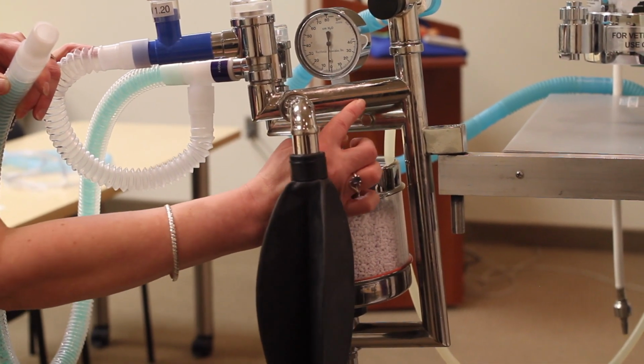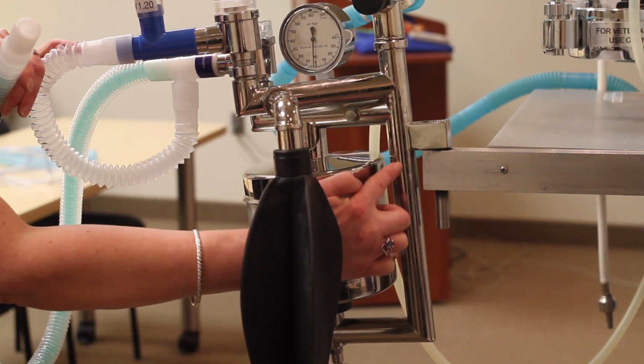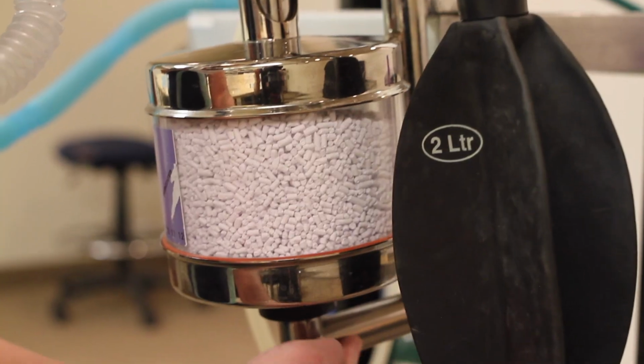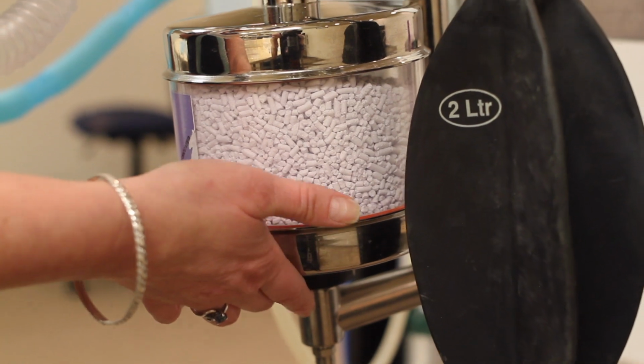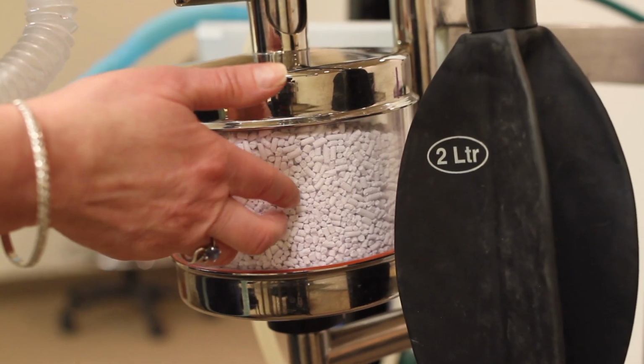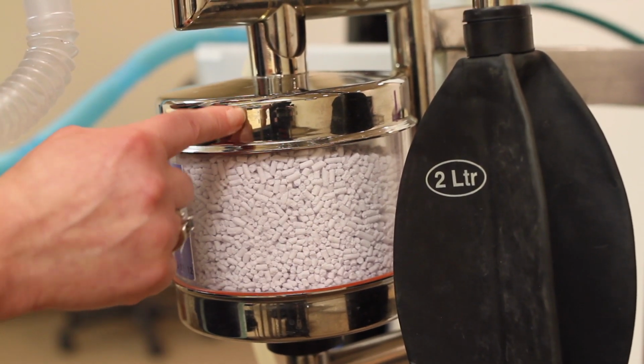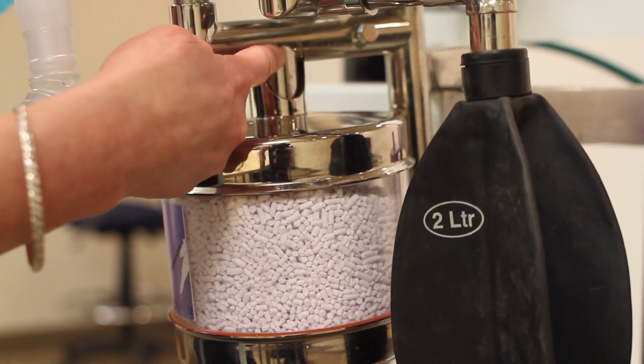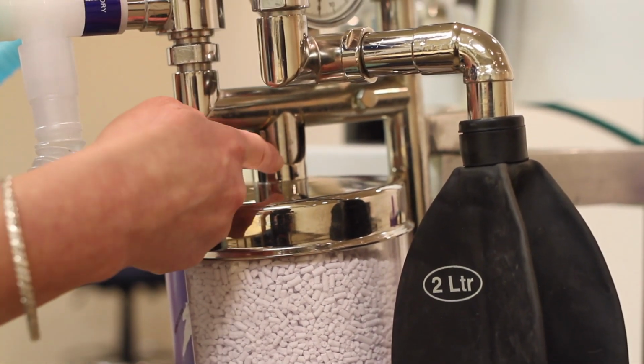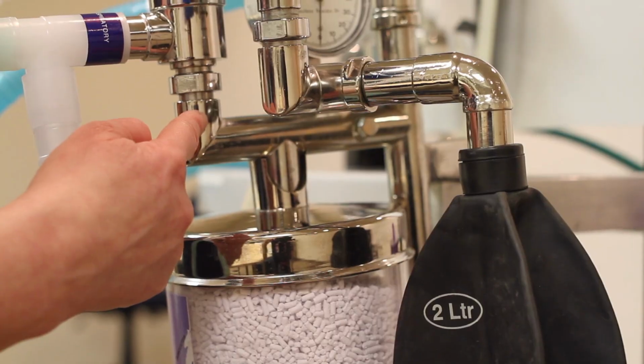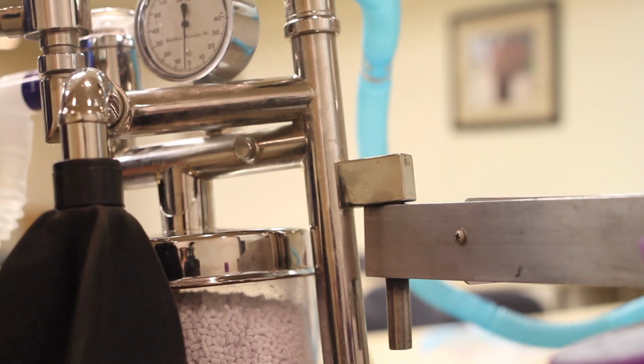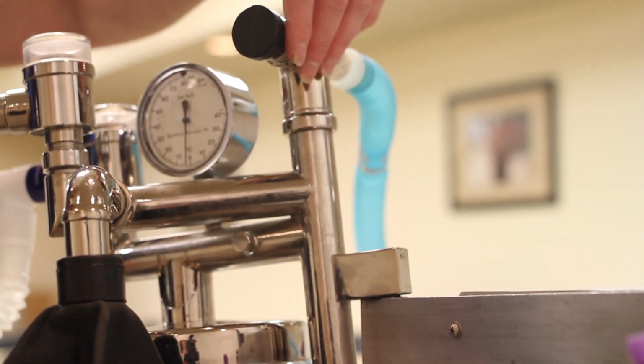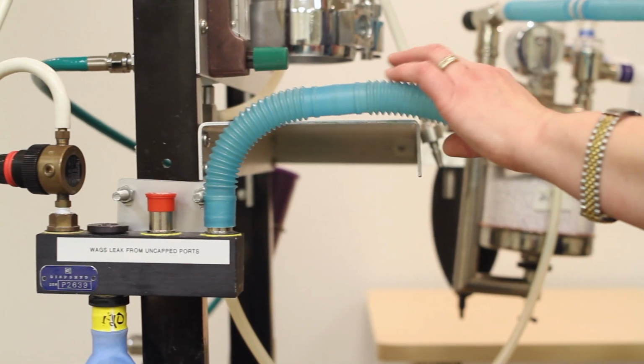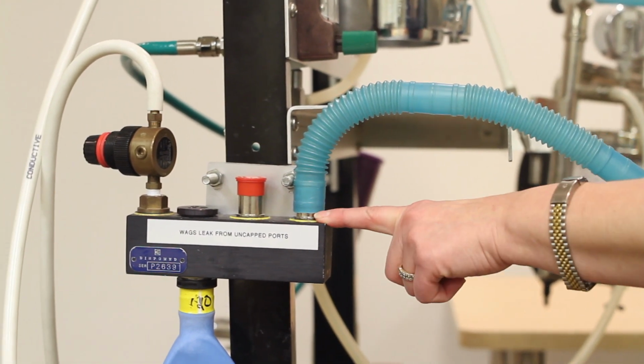The gas continues to travel down through this tube, goes across here, and starts to percolate from the bottom through the top of the soda sorb assembly, rejoining the cold, fresh incoming gas at this location. The rest of the gas goes out through our scavenger pop-off and scavenger hose into the active scavenger interface.